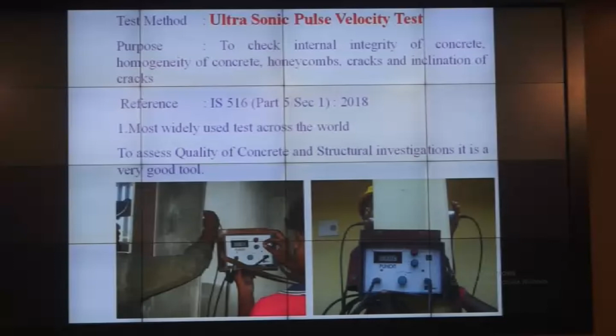See, left and right hand, somebody is holding those 2 steel things. They are probes. One will send the ultrasonic pulses this side, the other one will receive them. So the time taken to pass from this end to that end is measured by this instrument. The instrument also measures the distance travelled between the 2 transducers, and it calculates the velocity in kilometers per second. IS 516 also says about that.